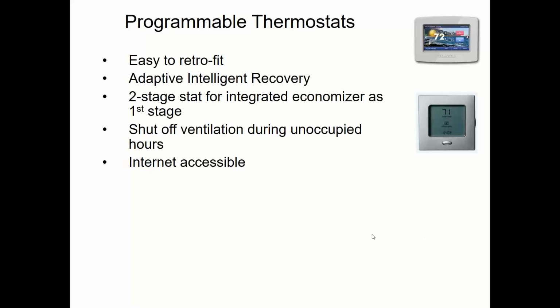Mike asks, what about going into setback an hour before the building is officially considered unoccupied? That'll save more energy. So if your building's going to go unoccupied at 5 p.m. and you want to go on to the unoccupied set points at 4 p.m., it'll save more energy, right? It's an extra hour of relaxed set points. The debate you'll get into is whether you need to ventilate during that time frame. That's going to be your challenge, because for ventilation code, you're probably going to want to do that.